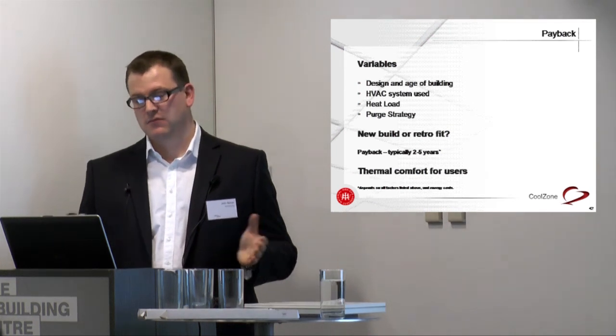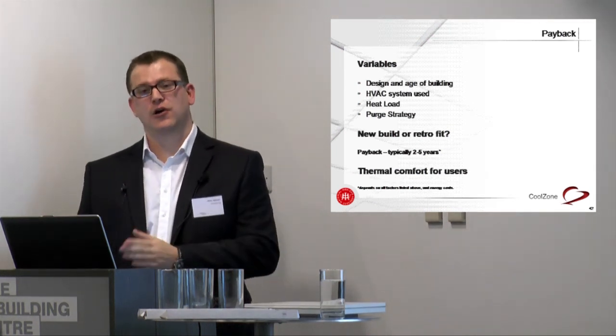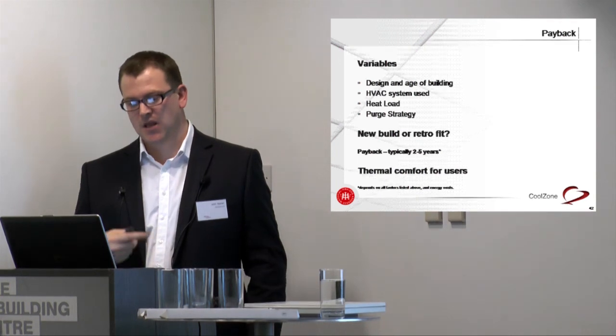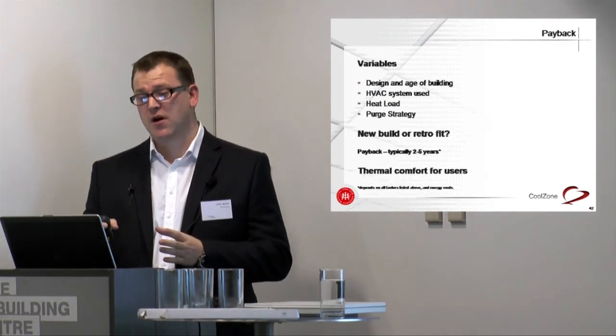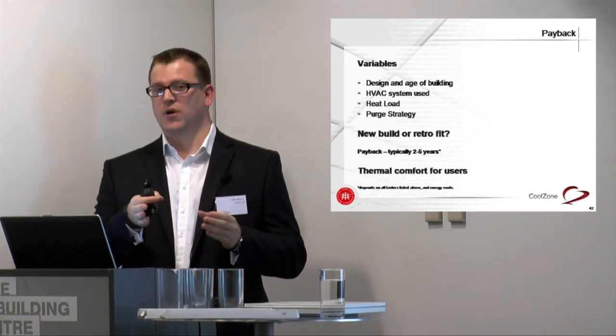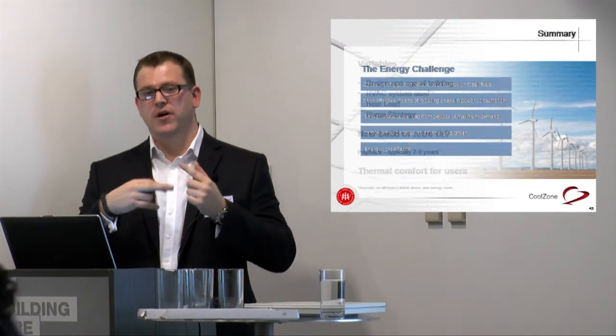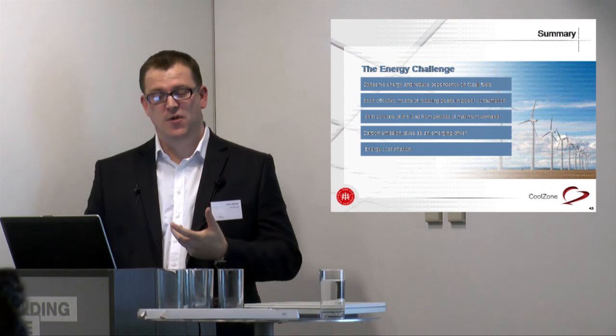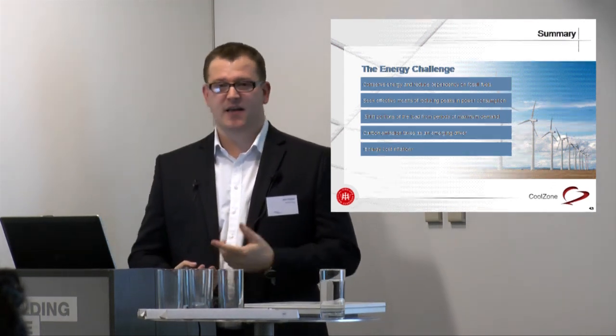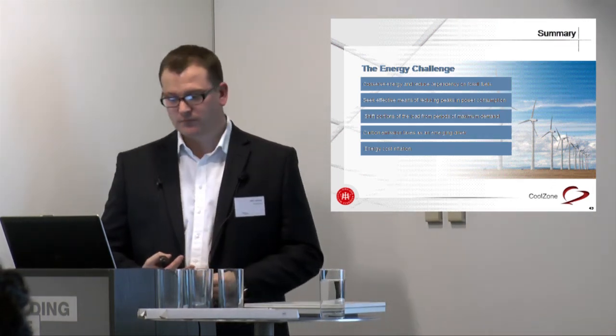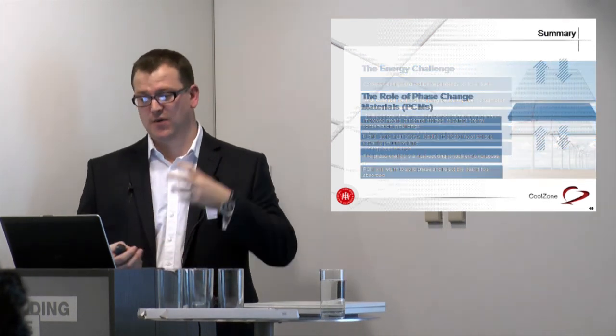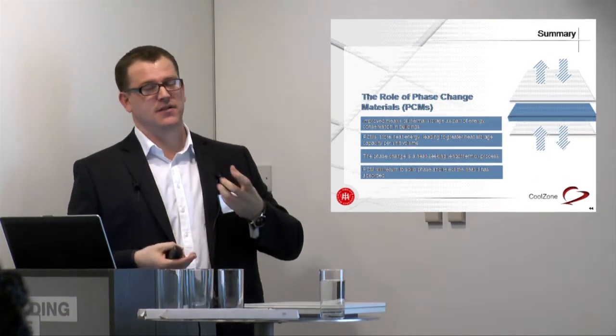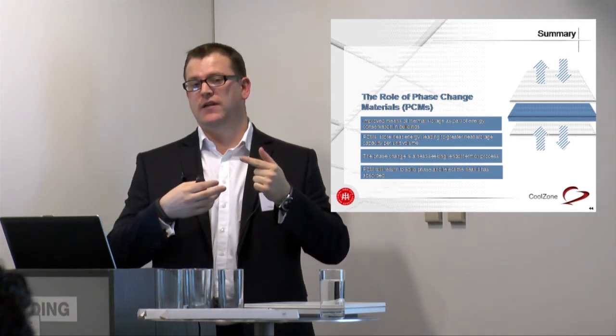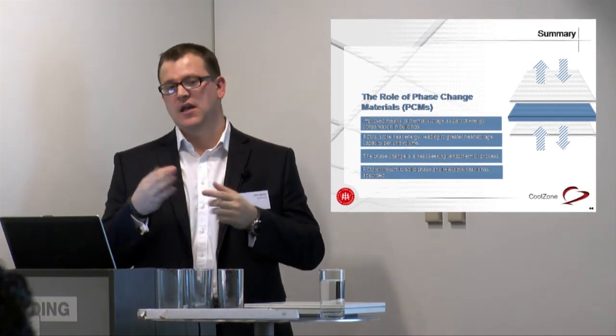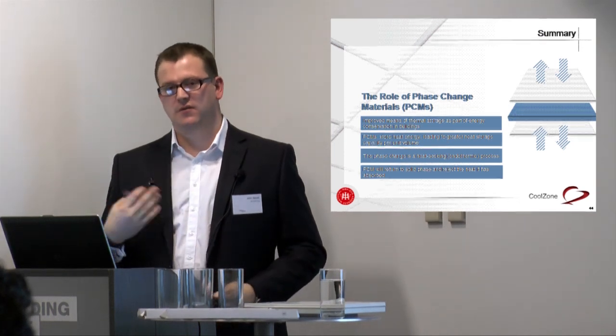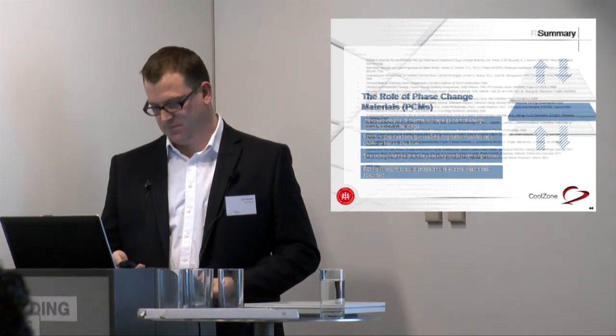So it doesn't matter, as long as the tile is reset for 9 o'clock, what strategy we use. In some cases the coldest part of the night is actually between 5 and 6 in the morning, so if you can do a super purge at that time, it might be as simple as a caretaker coming in and opening a window, or it can be more sophisticated, with thermocouples in the tiles that tell you whether it's molten or solid, telling you where it needs to be purged, which can automate the ventilation to activate the purge.